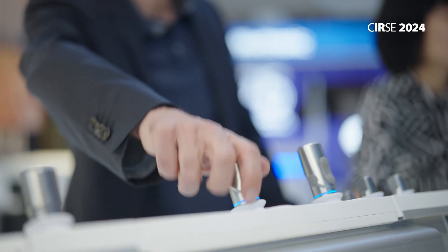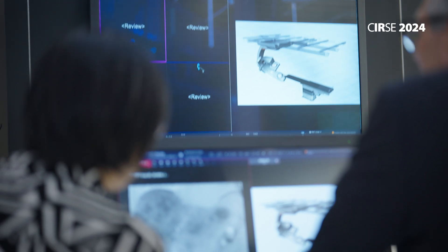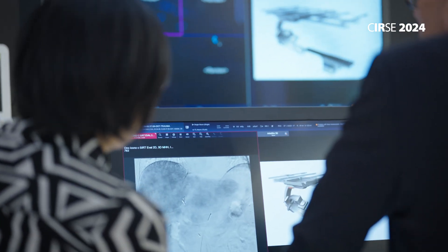Another feature of the Icono that we find extremely useful is the needle guidance function. The needle guidance function allows you to do CT-guided interventions on the angiography system. You import your 3D CT or MR data sets into the Icono.